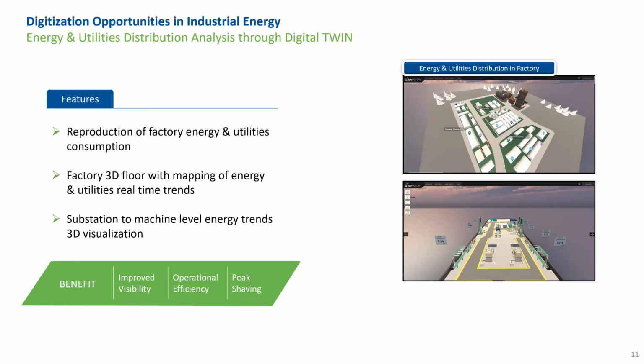You could measure peak shaving by equipment by its time of use during the day, and maybe shift it to an off shift because it's a high energy consumption item during peak demand periods with the utility. You can understand potential equipment upgrades and improvements, identify idle equipment that may be powered but not producing, and set up energy consumption alerts for each piece of equipment.